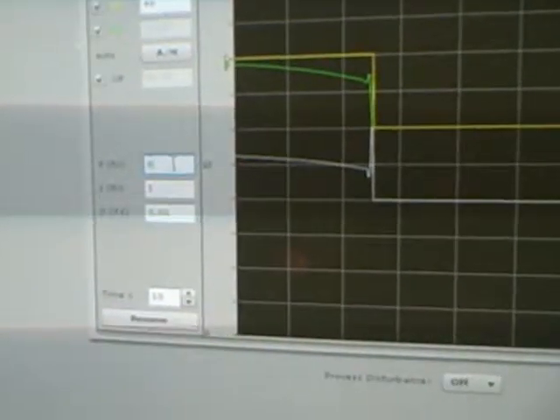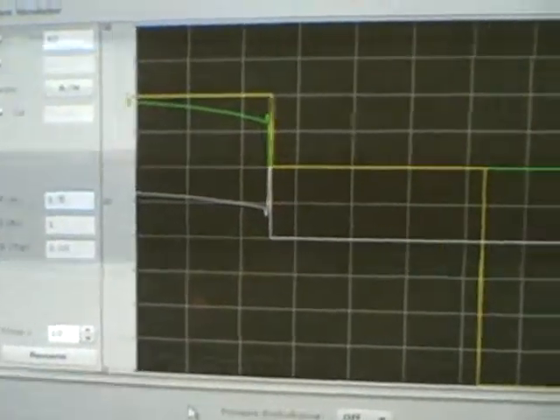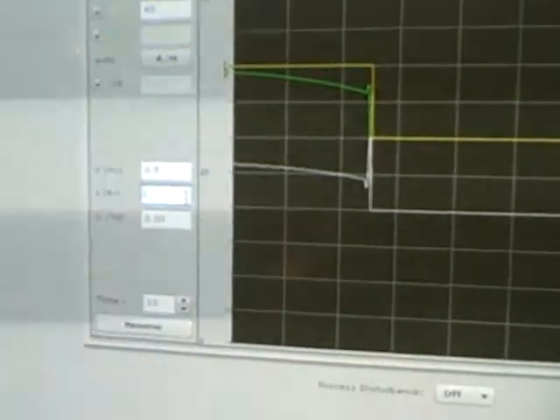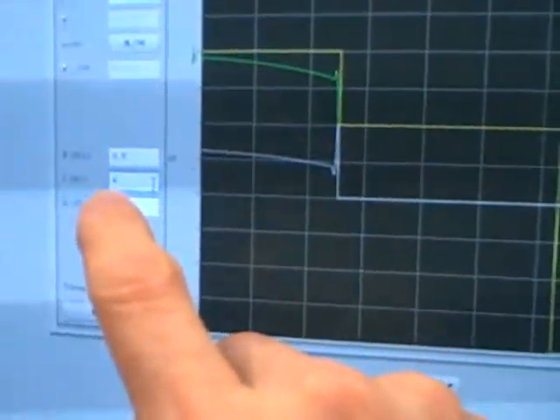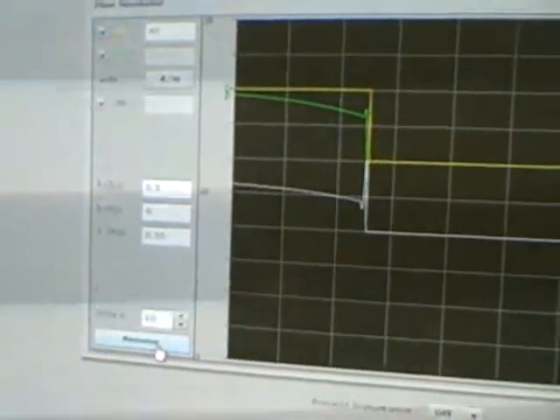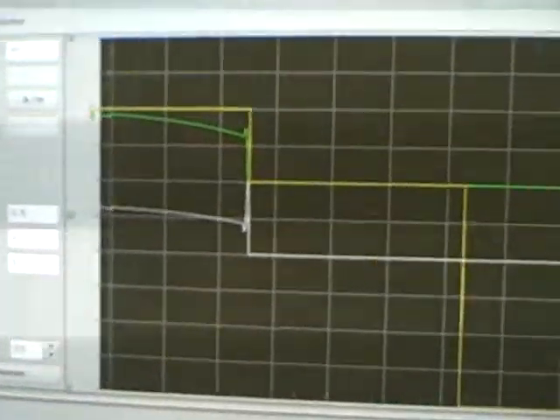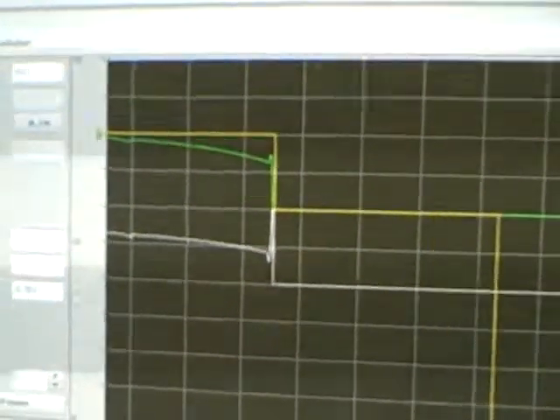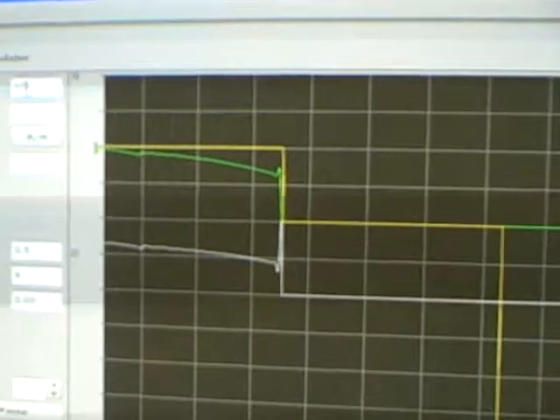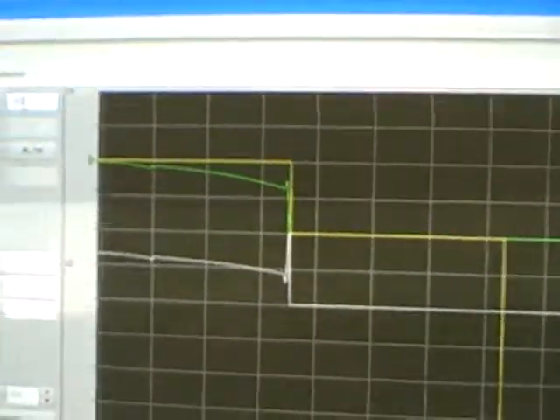So I'm going to go over here and change my gain from a gain of 1 down to a gain of 1 half. Now I can see already that my integral action is not strong enough. I'm taking a long, long time to build up to set points, so I'm going to plug in a more aggressive integral. I'm going to go with 4 repeats per minute. This is repeats per minute, not minutes per repeat, so a bigger number means more aggressive. I'll resume the simulation and see what happens. I'll let it reach set point, then I'll give it another set point change down to 30%. Let's see the response.